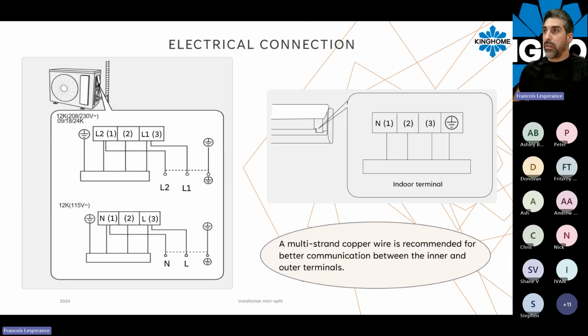On the electrical portion of the system, for a ductless unit like that, it's pretty easy. It's pretty much plug and play. All you need is to bring the power from the electrical panel to the outdoor unit, on L1 and L2. Then you will have three terminals going from the outdoor unit to the indoor unit, and you connect your terminals 1, 2, 3 to the same terminals 1, 2, 3 on the indoor portion.